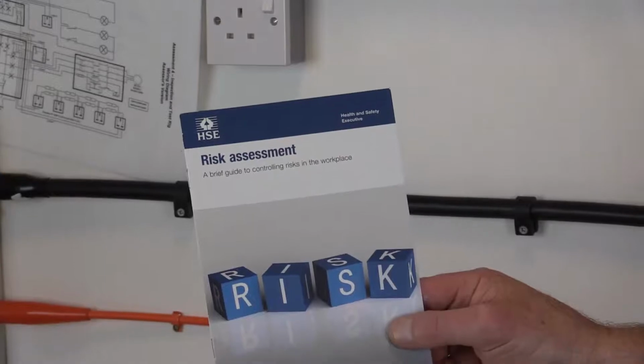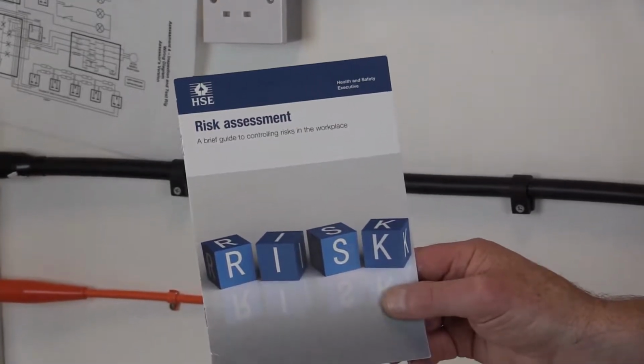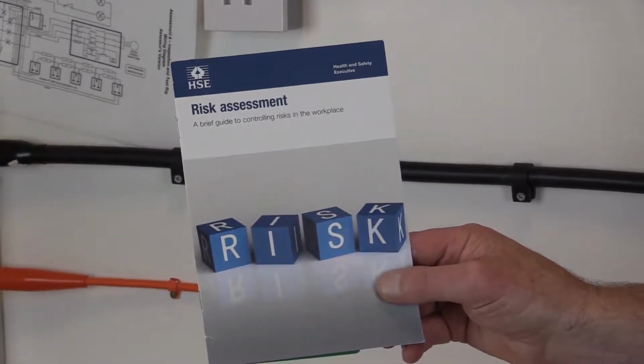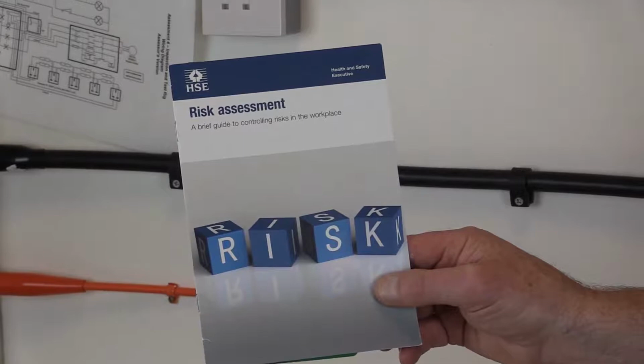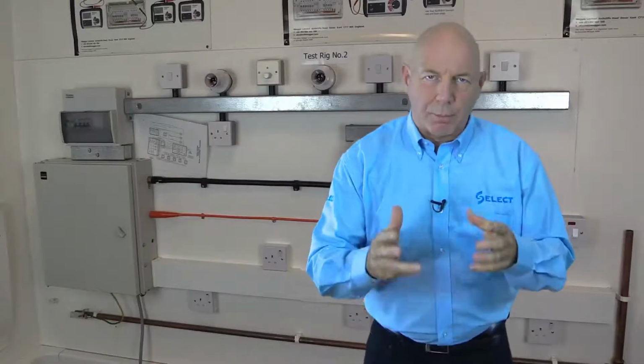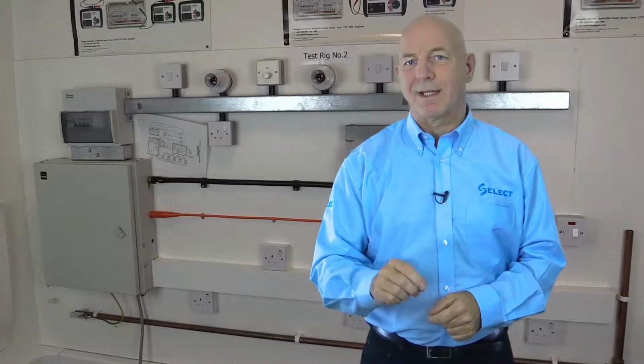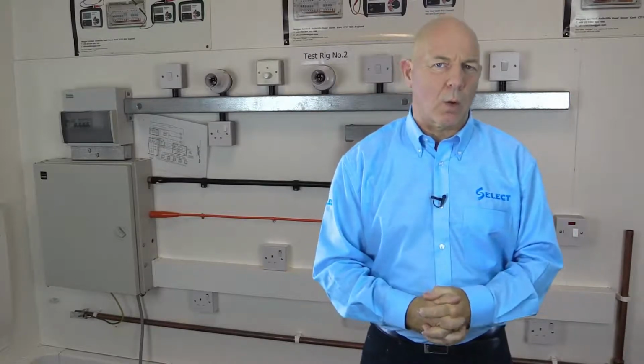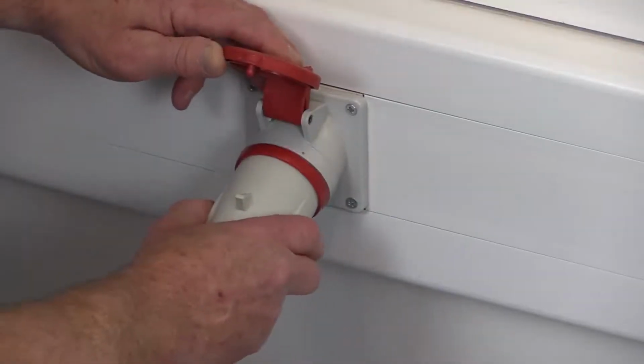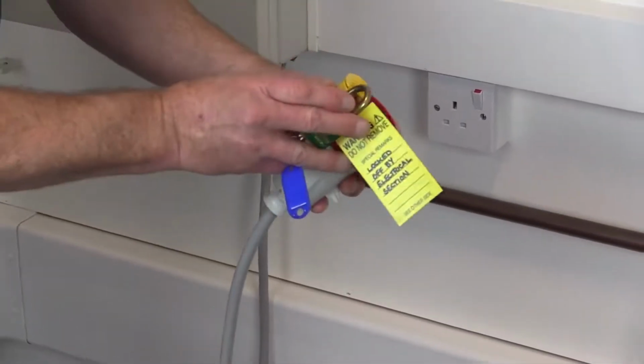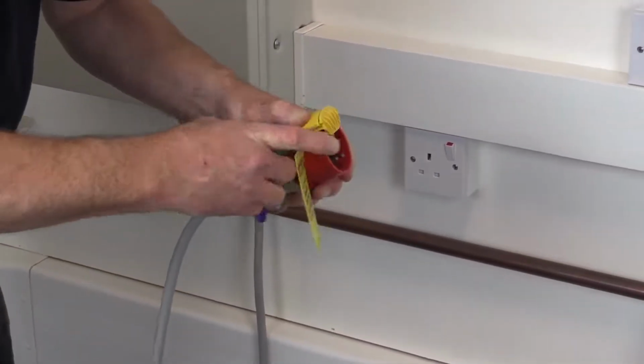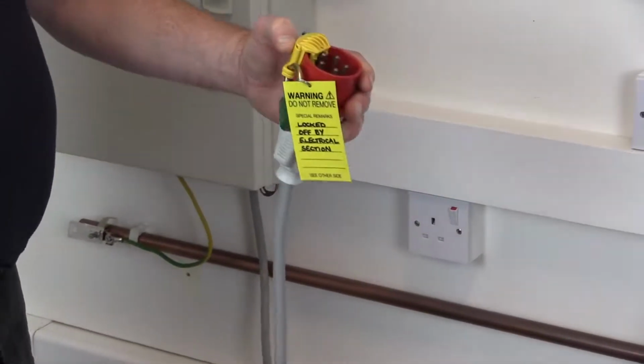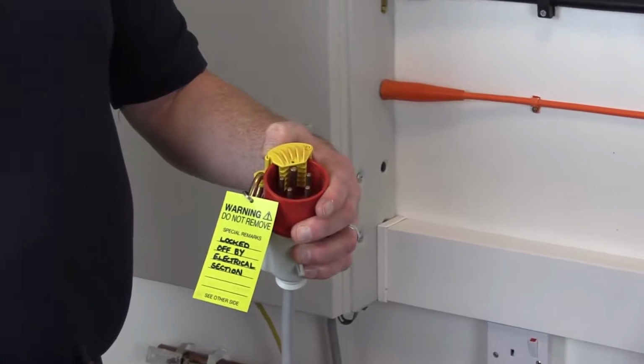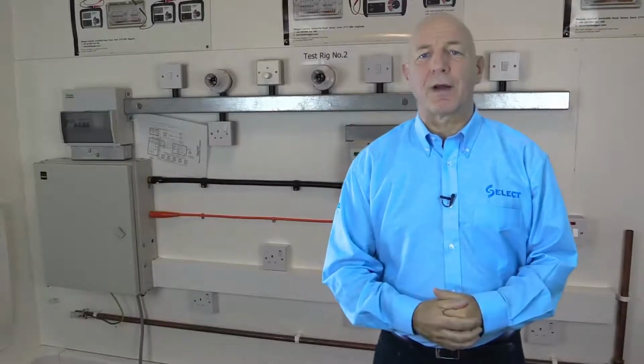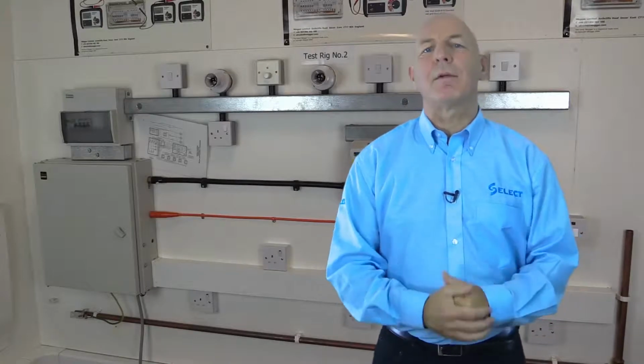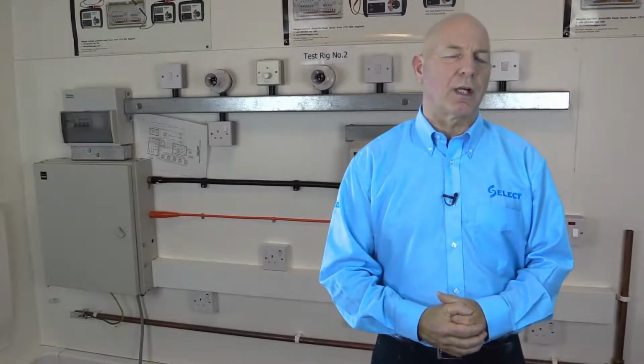And a risk assessment should be carried out, and where necessary, measures put in place, including using appropriate personal protective equipment before testing begins. Now, it's important that appropriate inspection is carried out before commencing any tests, as per Regulation 611.1. This shall normally be done with the supply disconnected and carried out during the erection of the electrical installation, as well as on its completion, to verify that all equipment has been selected and erected in accordance with BS 7671. And this should take account of the manufacturer's instructions, and that it's not visibly damaged or defective so as to impair the safety of the installation.